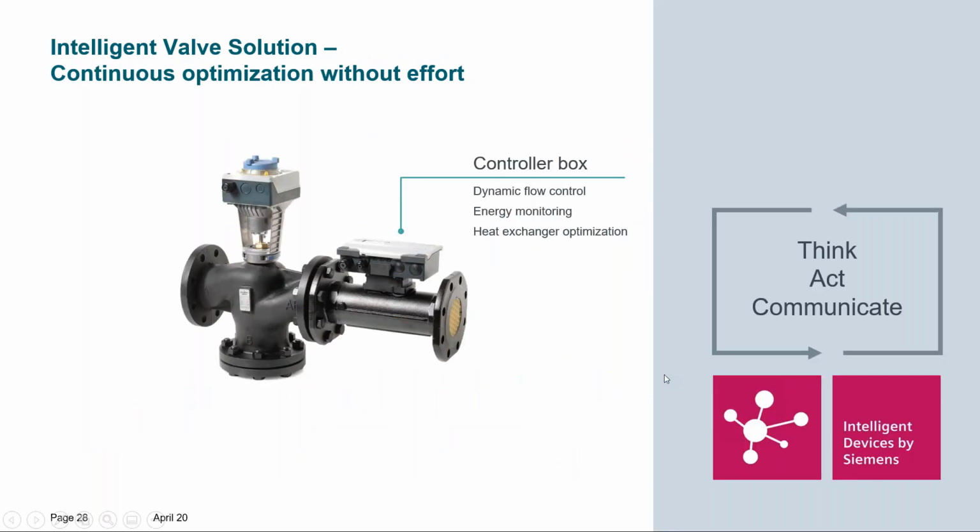Now we heard it already in the beginning. How is delta T influencing the energy efficiency and also the operation costs? Clearly, on the one hand side, we have seen with decreasing delta T, we will need more and more flow, which the chiller plant has to provide. And somewhere it's not even possible to increase the flow, and the different risers will start to starve, not fully supplied with the right amount of power. And this is one topic. And the high flows also would need a very high amount of pumping energy on that side.